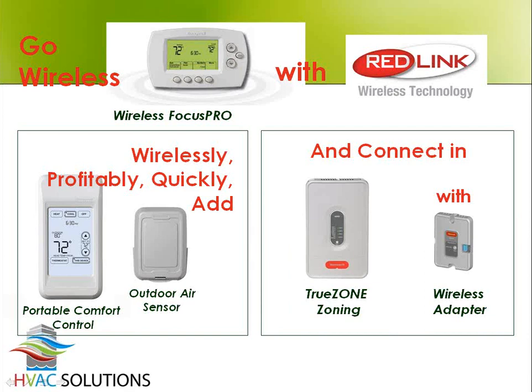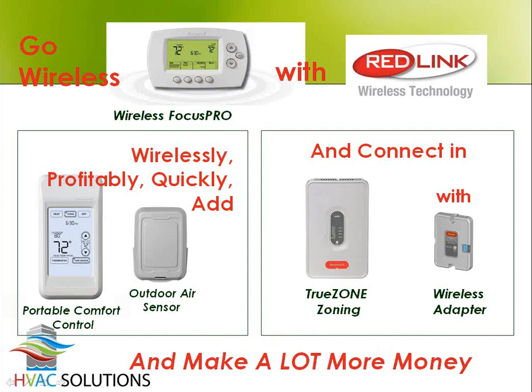So the Honeywell TrueZone panel also has a wireless adapter available for it, and you'll have some wires between the two of those, but they'll be sitting right next to each other on the wall downstairs. And you'll obviously have wires from the zoning panel to the dampers, but all the stats in the space could be 100% wireless. So it should help you improve profit if you can install a zoning system without as much of the labor. And a lot of times, yeah, there's a lot of work in putting the dampers in and getting to some rough spots with the dampers, but the other half of the equation is getting wires chased all over the house. If you can avoid that half of the equation and go wireless, it might make sense for you.